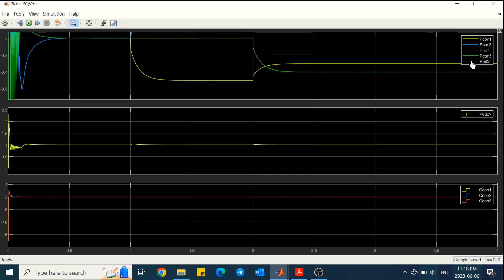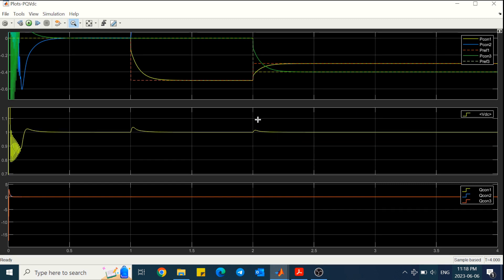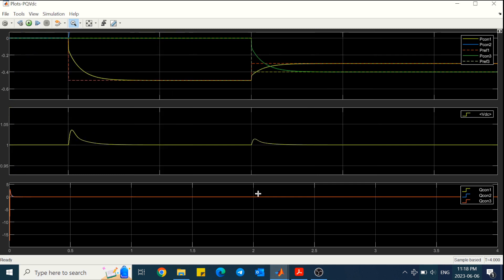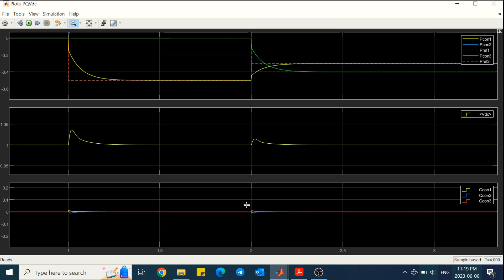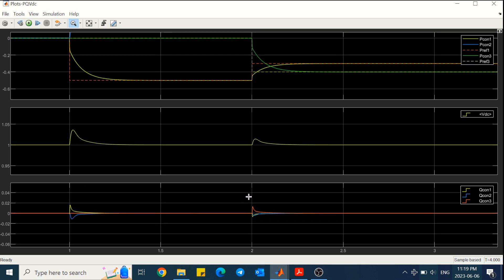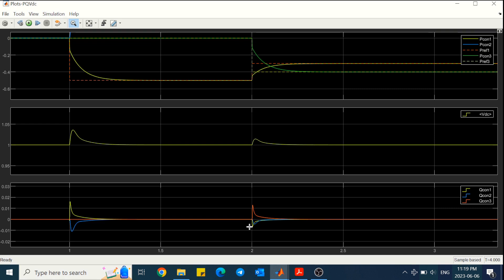To be accurate, converter 1 is absorbing 0.2 per unit of this injected power and converter 2 is taking care of the remaining 0.2 per unit, because we wanted to share it equally. If it was 0.1 for converter 1, the rest would be extracted by converter 2 which is in VDC control mode. Also in this case we see some transient in DC link, and reactive power is 0 because the setpoint is 0. We see some transient in reactive powers as well because of interactions between control loops.